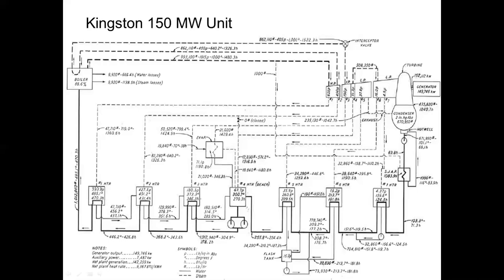These are the design values for the plant: 149,746 kW, which is perilously close to 150 megawatts. Auxiliary power runs the cycle, and net plant generation is shown here. Heat rate is the way the power industry states efficiency — 9,367 BTUs of input into the cycle to generate one net kilowatt-hour. Lower is better; if we make it more efficient, that 9,367 might go down to 9,200 BTUs per kilowatt-hour.